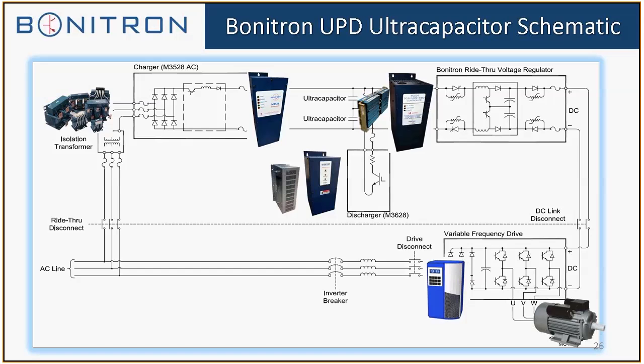The discharger will discharge the caps within seconds, and then it's safe to open the cabinet and get in and look at things and do maintenance or whatever you have to do. Then the voltage regulator is connected to the other side of the ultracapacitors, or energy storage. It pulls the energy out of the cap bank, rectifies it, boosts it, and puts it to the DC bus positive and negative connections of the VFD. Once again, you're connecting the VFD right across the DC bus at the bus capacitors.